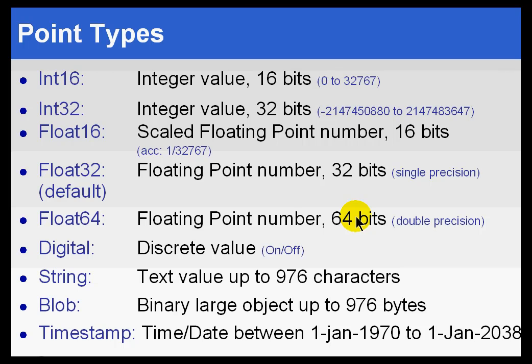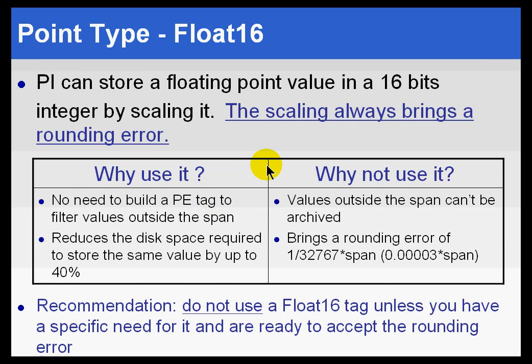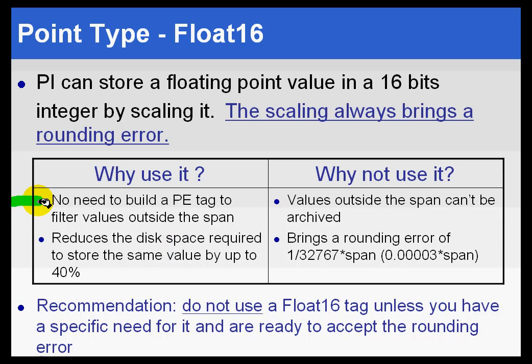We looked at point types a little bit earlier. Let's concentrate now on some unusual point types. Let's look at Float 16 first. Float 16 is a type of point designed to save on disk space and to maintain compatibility with earlier versions of PI. It has a couple of advantages — it's smaller, as the name would imply with 16 versus Float 32. But it is not as accurate.